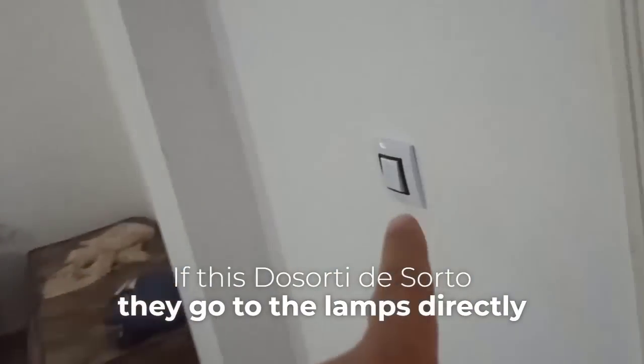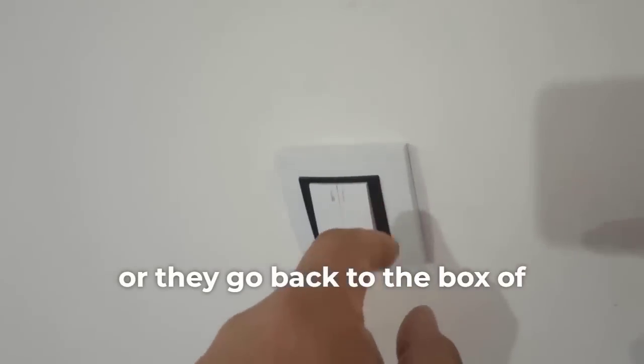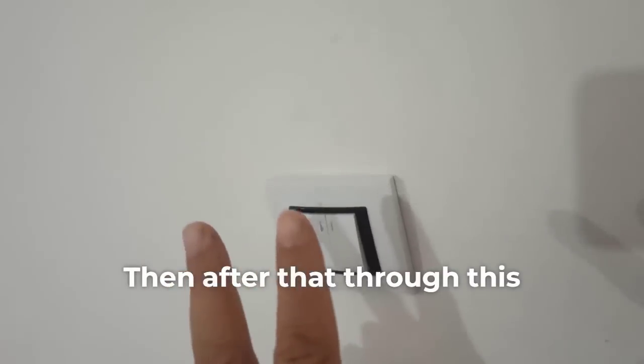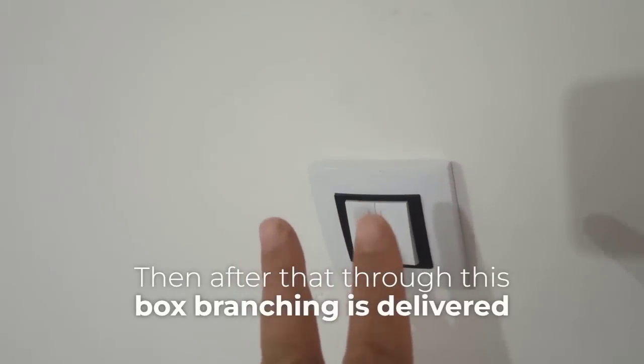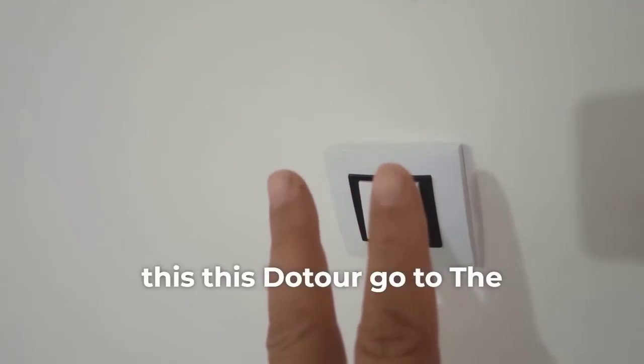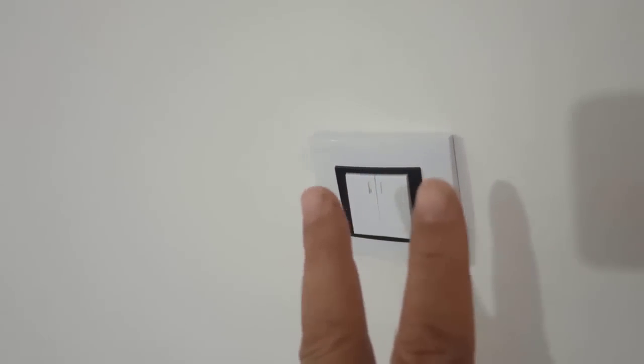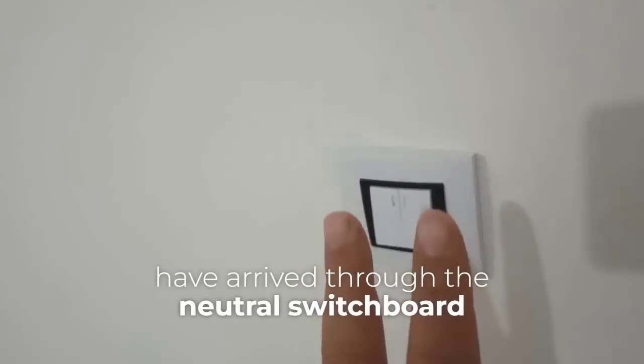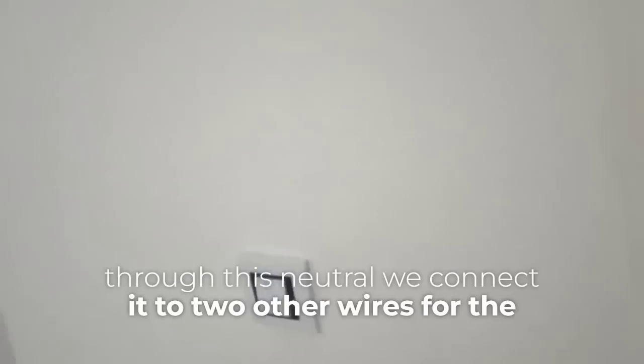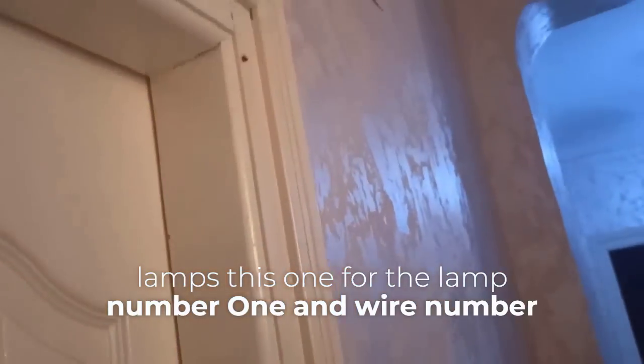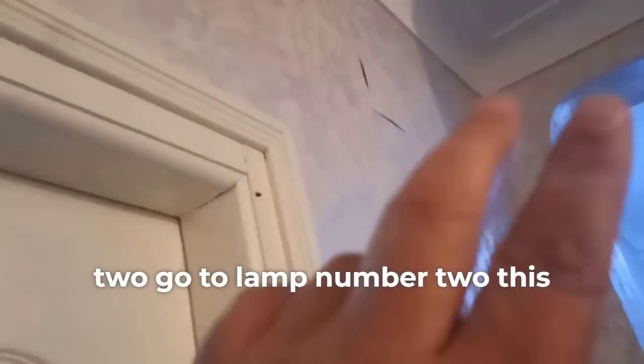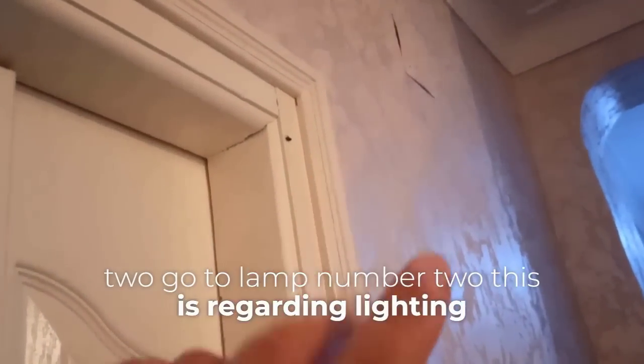These outputs go to the lamps directly or they go back to the branching box. Then after that, through this branching box, the wires are delivered to the lamps. The lamps are here, and then we have the neutral arriving from the switchboard to this branching box. We connect this neutral to 2 other wires for the lamps: this one for lamp number 1 and wire number 2 goes to lamp number 2. This is regarding lighting.